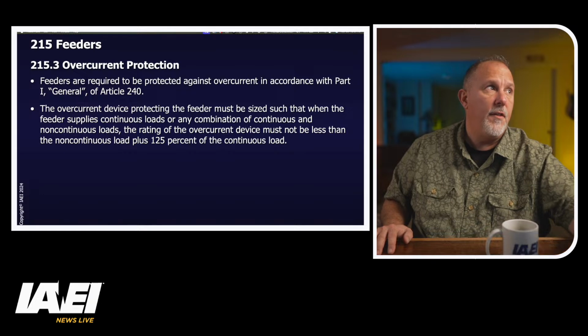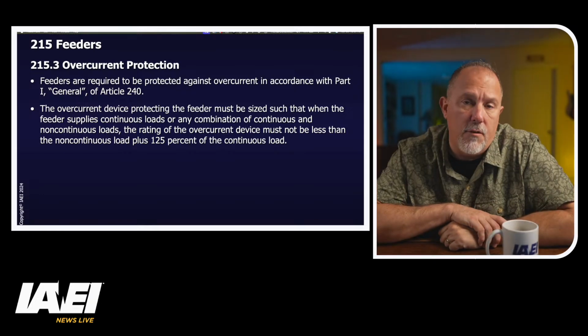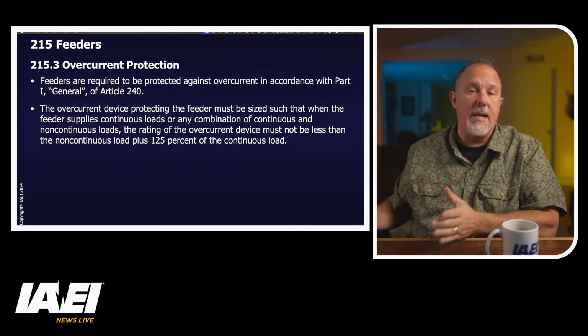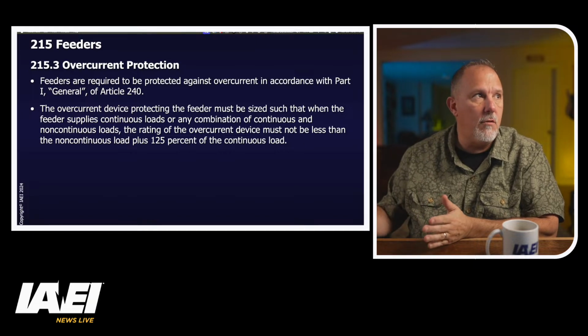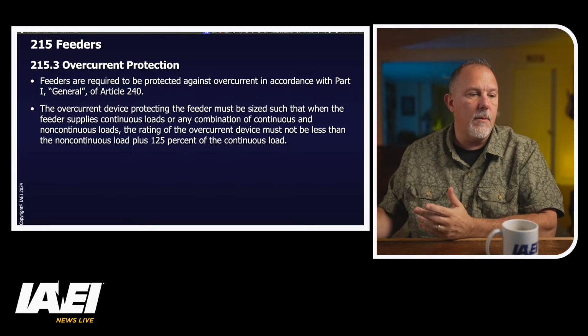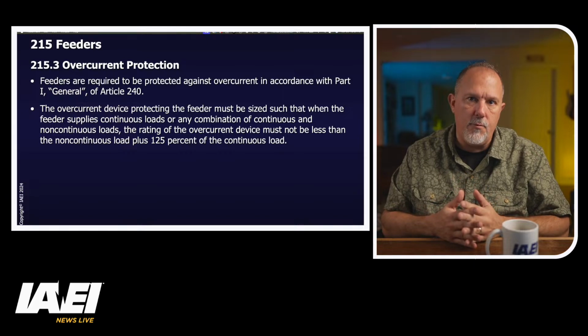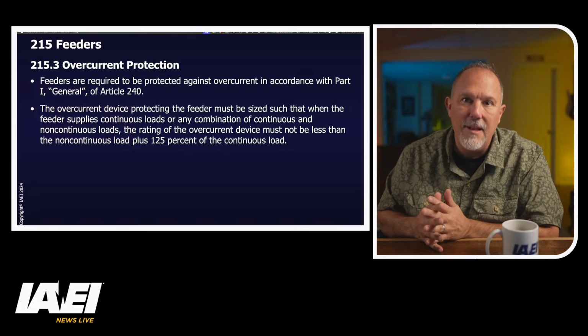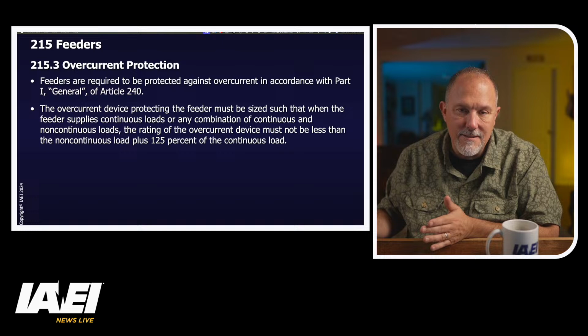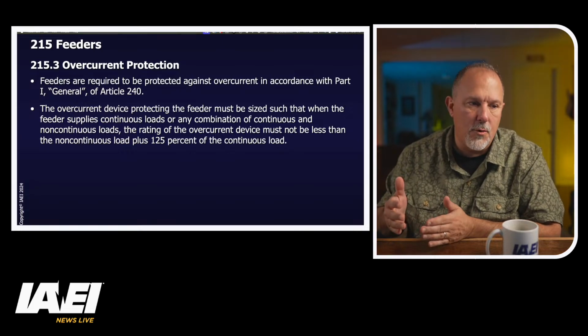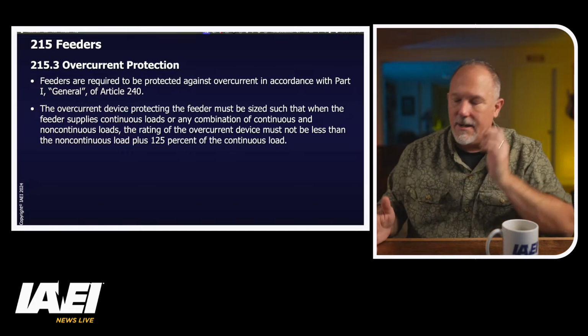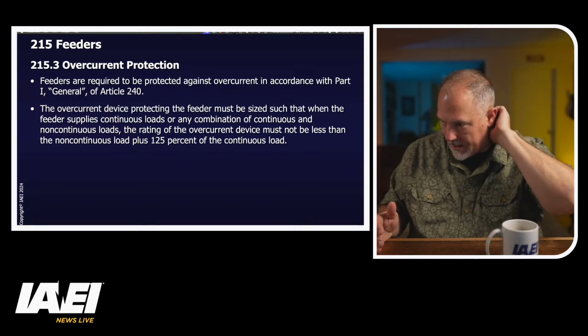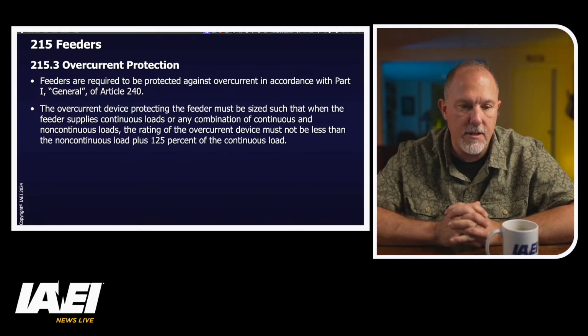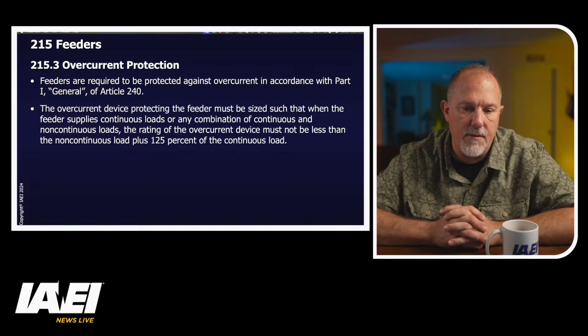So this 215.3 overcurrent protection really opens up a can of worms because it points to 240. And you're into Article 240 Part 1, which then brings in Part 2, the location in a circuit. And you get to your feeder tap requirements, provisions. So you have to be mindful of your feeder taps as part of 240 as well.